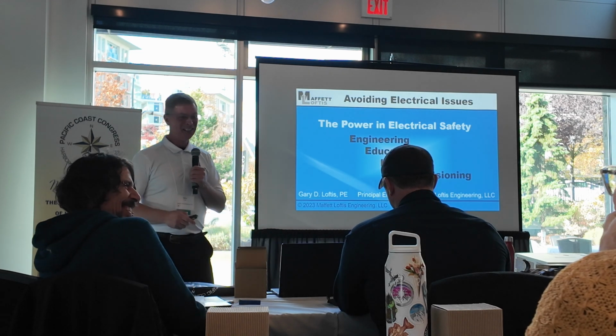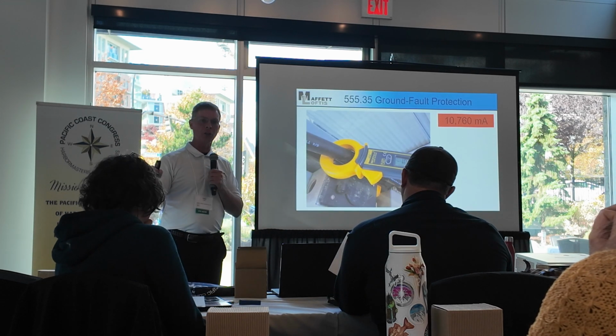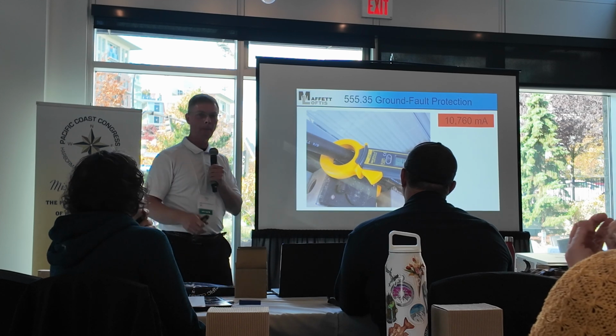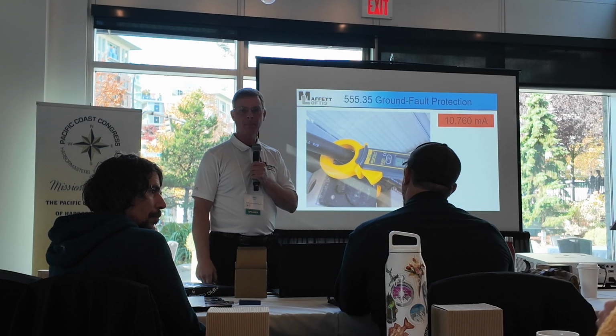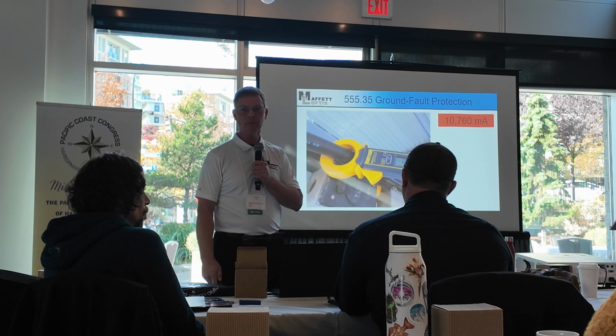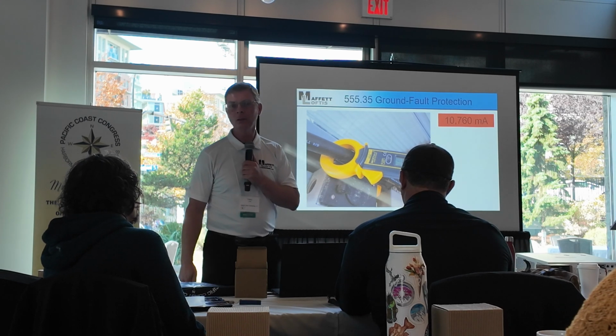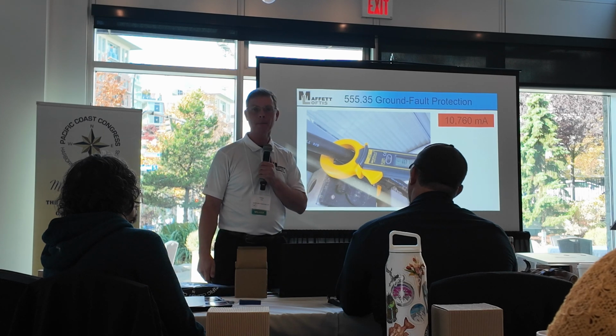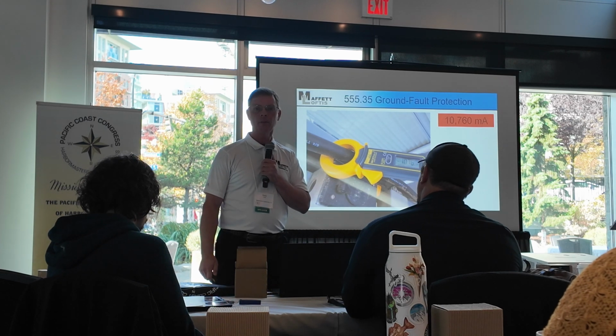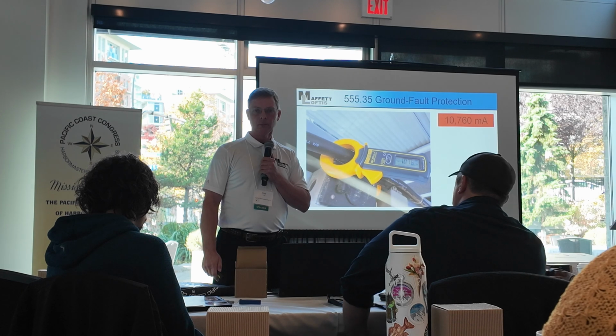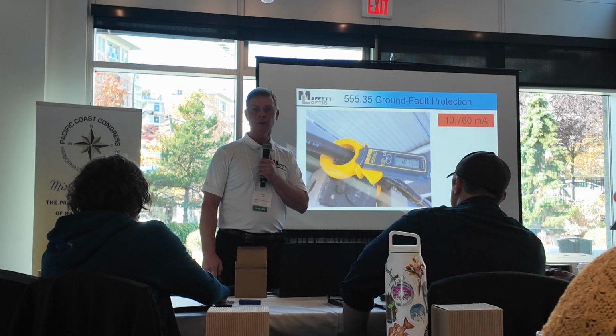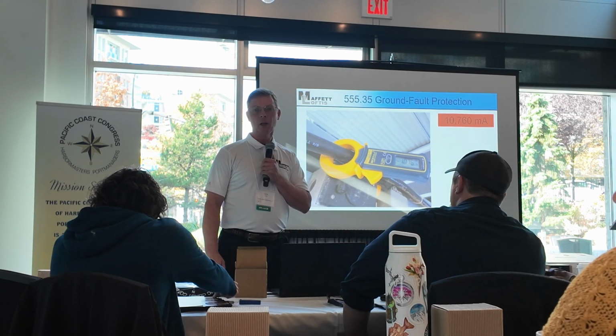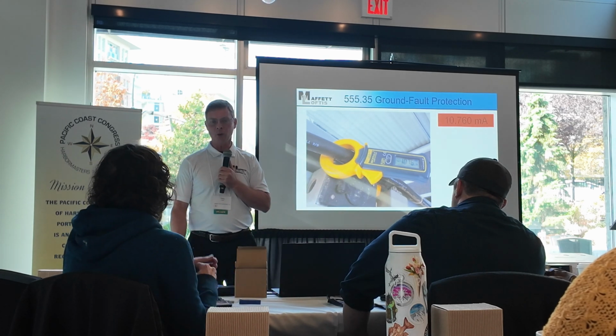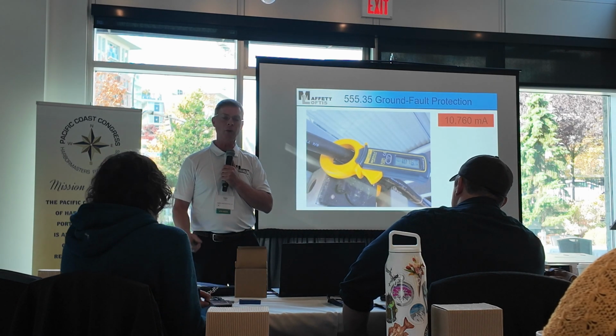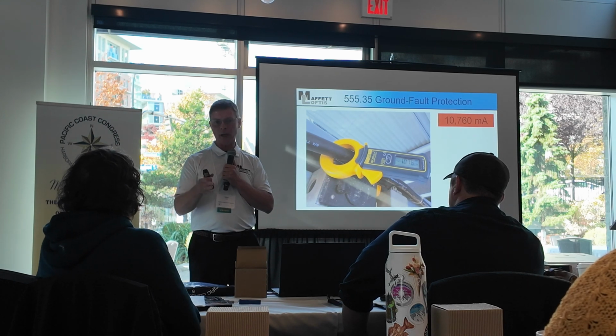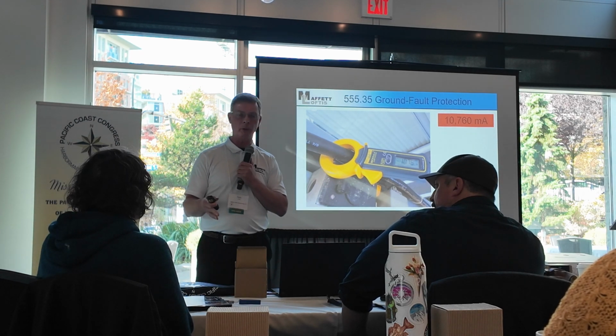Okay, great. All right. Well, are there any questions on ground fault protection? I'm going to get into a couple other things. Yes. What's your view on PEN faults? Is this something that they're considering? I know there's a lot of discussion happening in Europe around that. About what? PEN faults. If earth and neutral get severed, there's no connection between these two anymore, and it would essentially require a switch or a relay on earth. Right, you would actually have to open up the earth line as well. There's been talk about it, and what you're really talking about is ground fault monitoring. Or not ground fault, ground monitoring. Yeah, grounding conductor monitoring, to monitor the grounding conductor.